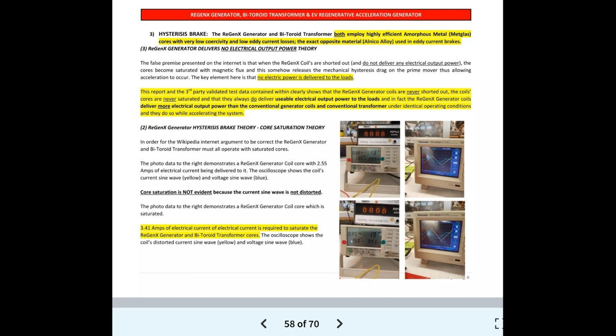The photo data to the right demonstrates a ReGenX generator coil core which is saturated. 3.41 amps of electrical current is required to saturate the ReGenX generator and Bi-toroid transformer cores. The oscilloscope shows the coil's distorted current sine wave, yellow, and voltage sine wave, blue. Core saturation is evident, because the current sine wave is clearly distorted. In order to saturate the ReGenX generator and Bi-toroid transformer Metglas cores, a minimum of 3.41 amps of electrical current is required. As flux density approaches saturation, the magnetic current waveform becomes distorted.